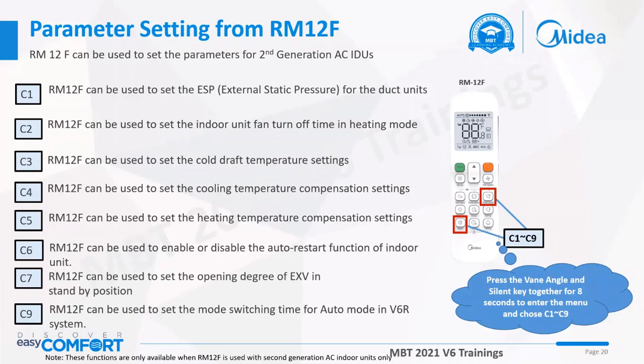So how to do those settings? So we can do it from our wireless controller as well. So you need to press the C1 to C9 button. You need to press this vane select and silent button together for 8 seconds, and then you will see the C menu coming up. So if you go to like C1, and then inside the C1, then you can set the external static pressure. There will be further options like 00, 01, 02, 03. Inside the manual, you have a detailed discussion about the meaning of each option.